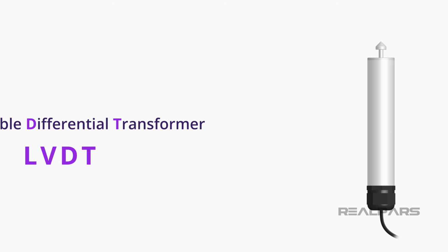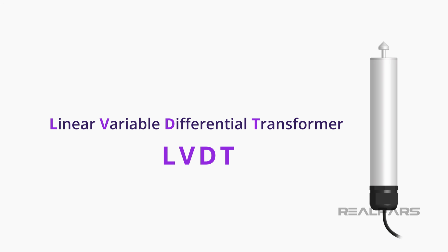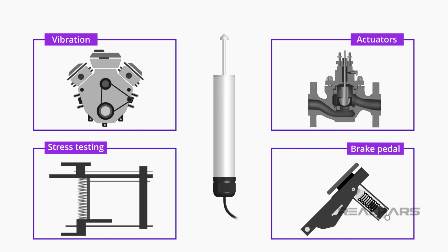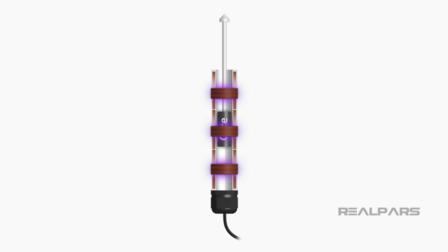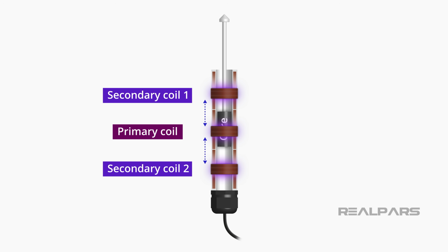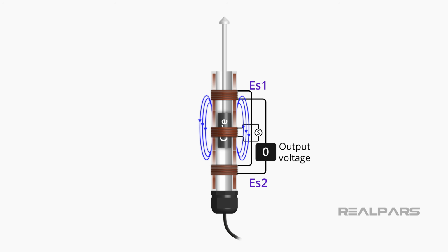Now, let's review what we have learned. Linear Variable Differential Transformer is a sensor used to convert linear motion into an electrical signal. They are used in numerous applications throughout many different industries to detect vibration, for stress testing, to measure actuator movement, etc. The LVDT consists of a hollow cylindrical array of coils, primary and secondary windings. An alternating magnetic field in the primary coil induces a magnetic field on both secondary coils. The magnetic fields induced on the secondary coils depend on the position of the cylindrical ferrous core that passes through the center of the hollowed tube.